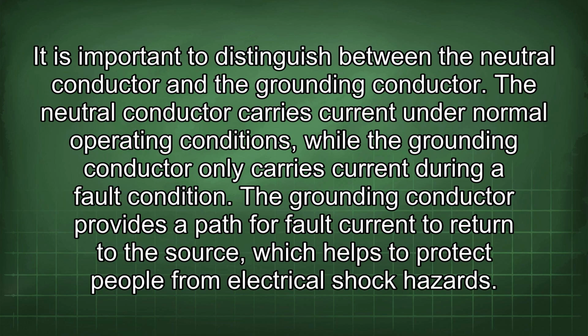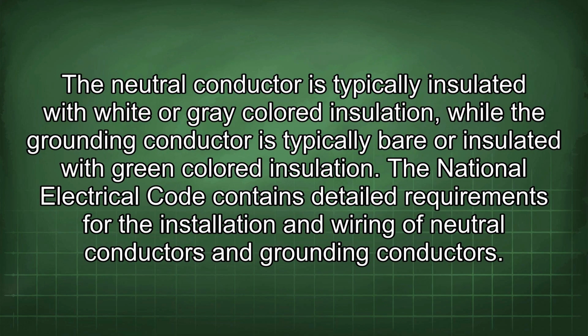It is important to distinguish between the neutral conductor and the grounding conductor. The neutral conductor carries current under normal operating conditions, while the grounding conductor only carries current during a fault condition. The grounding conductor provides a path for fault current to return to the source, which helps to protect people from electrical shock hazards. The neutral conductor is typically insulated with white or grey-colored insulation, while the grounding conductor is typically bare or insulated with green-colored insulation.